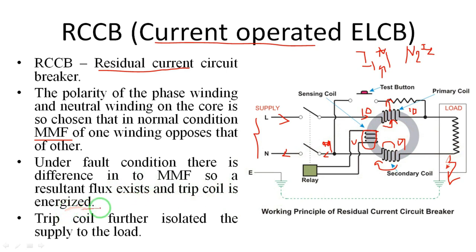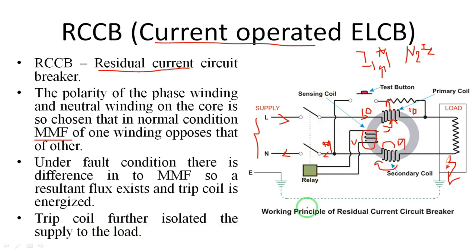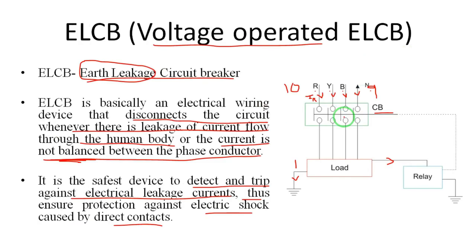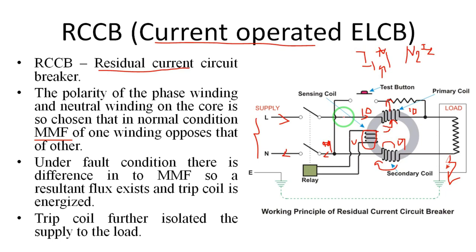Under fault conditions, the difference in MMF causes a resultant flux which energizes the trip coil. The resultant flux connected to the sensing coil induces a voltage, operating the relay, and the trip coil further isolates the supply to the load. This completes the working principle of the Residual Current Circuit Breaker. Thank you very much — if you have any doubts, please comment in the comment box.